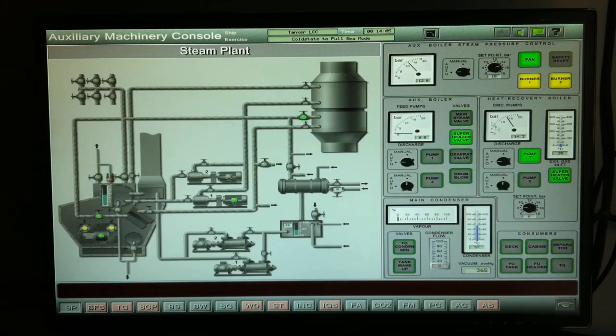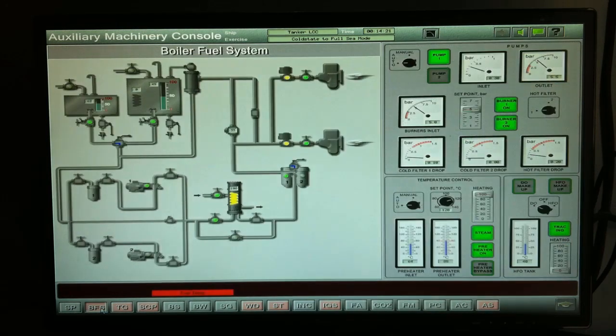Now, let's go back to our boiler. So we have 12 bars, no more alarm. Could now open your main steam valve for heating. Open your consumers, FO tank heating, separators, and then proceed to your fuel system of the boiler. You could see now that no more alarm on the fuel oil system of the boiler. So once you have no more alarms, you could already change over to heavy fuel oil.